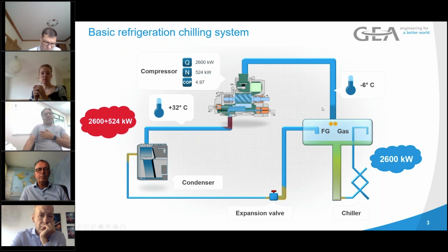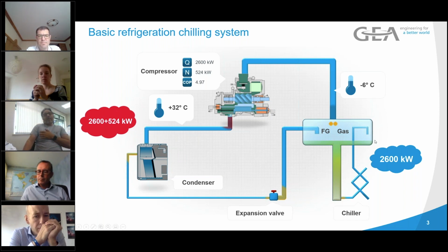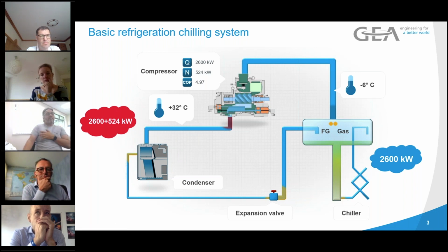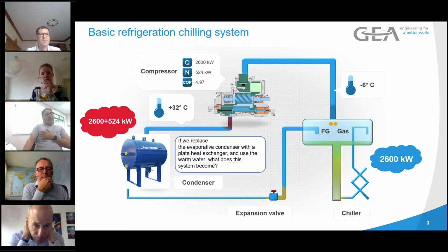If we just take the refrigeration process as an example, this is just a simple flooded ammonia system where the heat in around about -6 is 2.6 megawatts. We add the power of compression, and both get rejected at the condenser up on the roof. So we're rejecting around about 3.1 megawatts of heat. The only issue is the heat's not really at a useful temperature. If we wanted hot water at 30 odd degrees, we could just swap the condenser, but nobody really needs a lot of heat at 30 degrees in these factories.